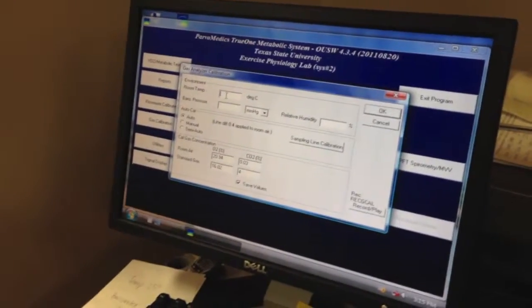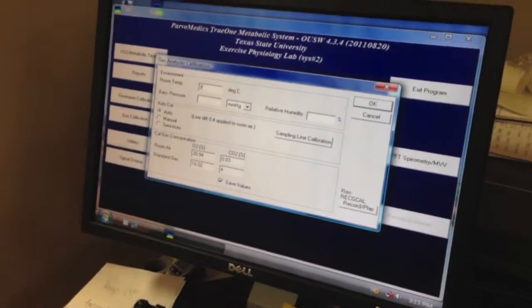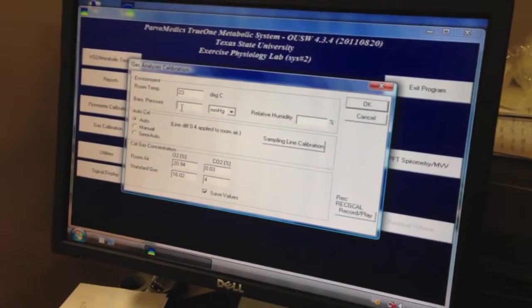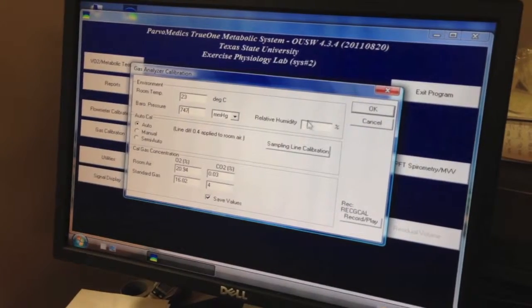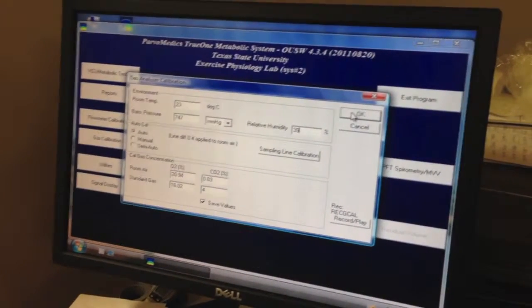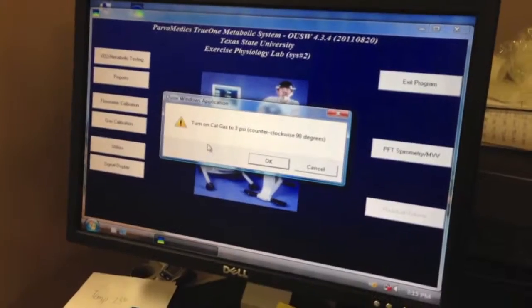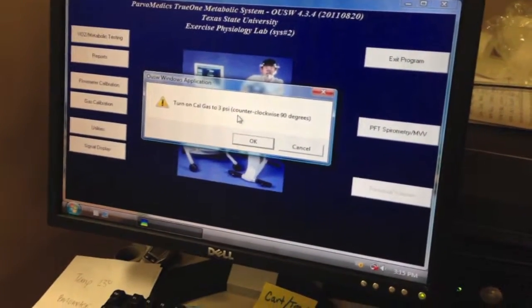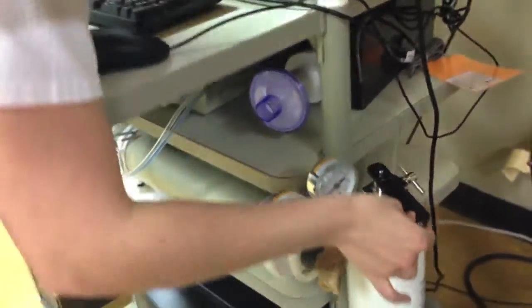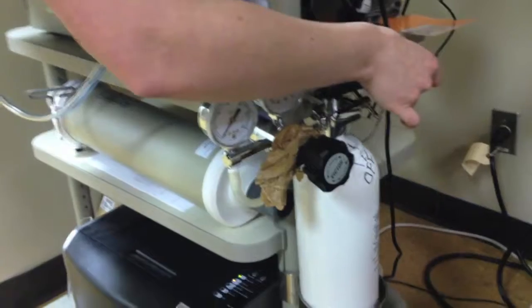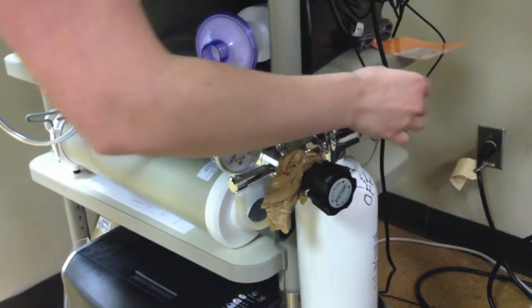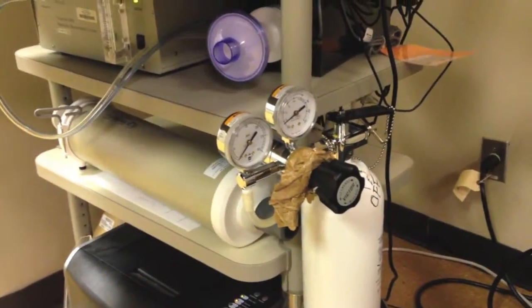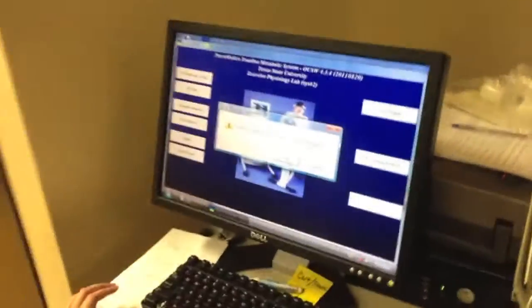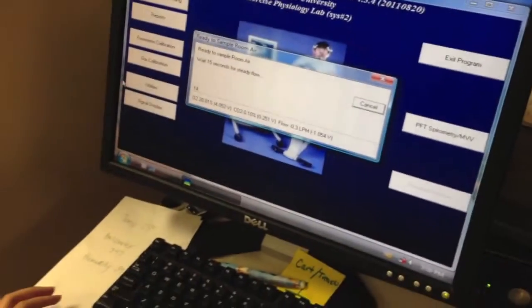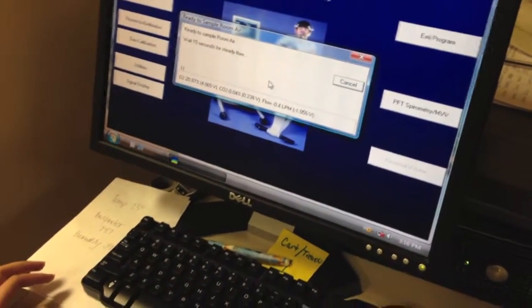The information for temperature, barometric pressure, and humidity is gathered from this device. After gathering the information, we want to input all of it into the computer, and then press OK. Now the computer is going to instruct us to turn on the gas to 3 psi, as shown here. Make sure that prior to turning on the gas that it's already set at 3 psi. So you'll turn it 90 degrees, and then you'll press OK and the computer will begin to sample the room air. It usually takes about 30 seconds.